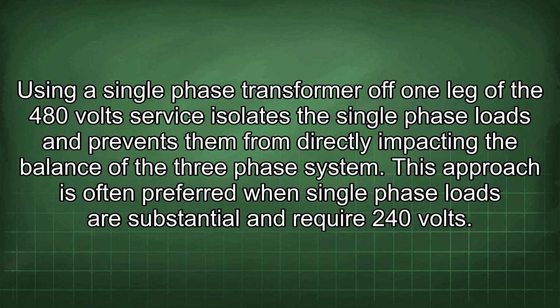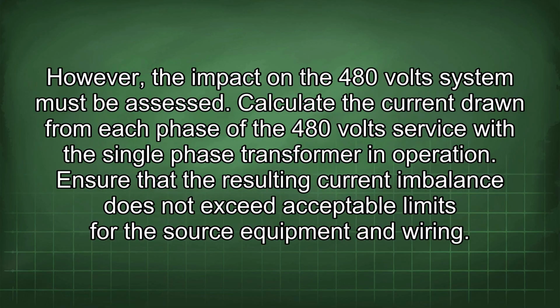Using a single-phase transformer off one leg of the 480 volt service isolates the single-phase loads and prevents them from directly impacting the balance of the three-phase system. This approach is often preferred when single-phase loads are substantial and require 240 volts. However, the impact on the 480 volt system must be assessed.